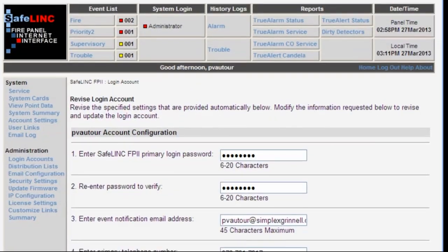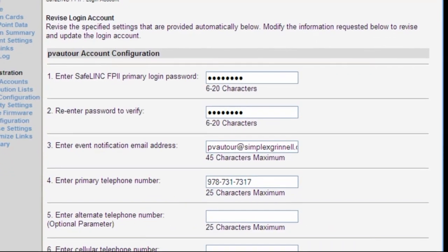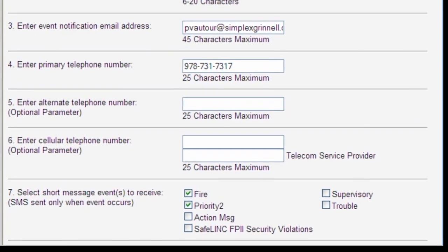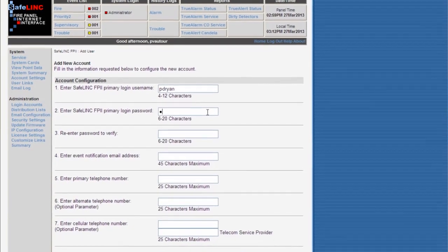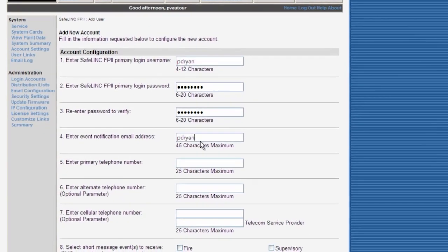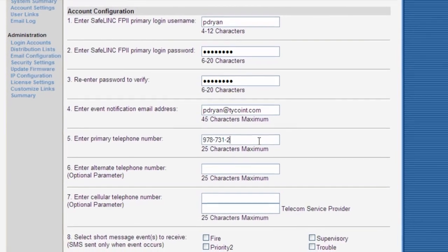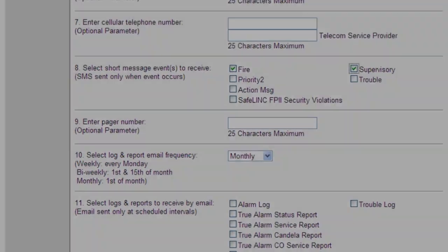Safelink also allows users to securely log into the Simplex fire alarm panel and review its status using standard browser software. I have the configuration screen for the Safelink card opened up on this PC. Each user account can be individually configured to receive some or all of the system events. For example, a building manager's account could be configured to receive only fire alarm and priority two events, but no troubles. Let me quickly add my colleague Peter Ryan into the Safelink card — I will add Peter so that he only gets priority one fire and supervisory points from the panel. Once the system is commissioned, the end user becomes the administrator for the system and takes care of the database going forward.